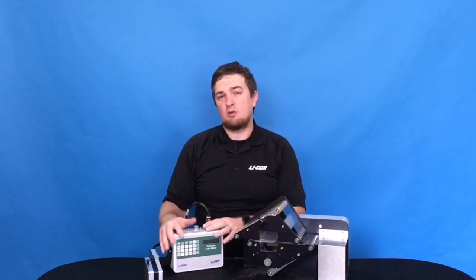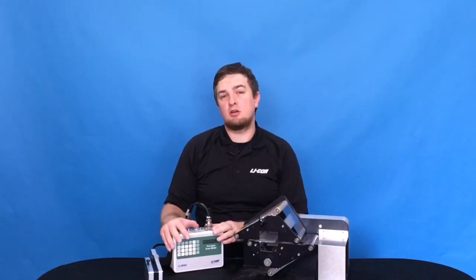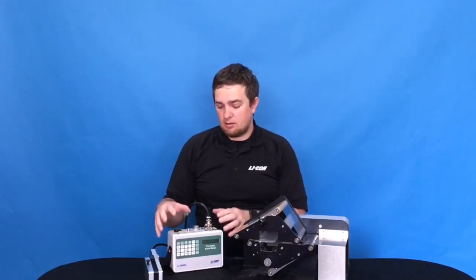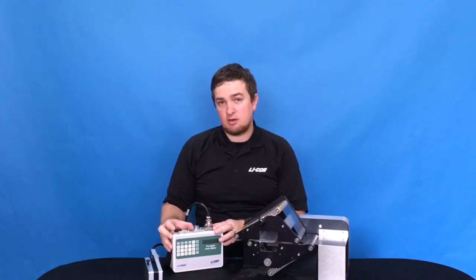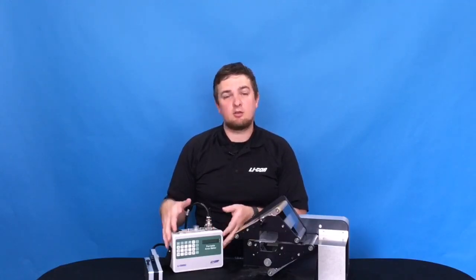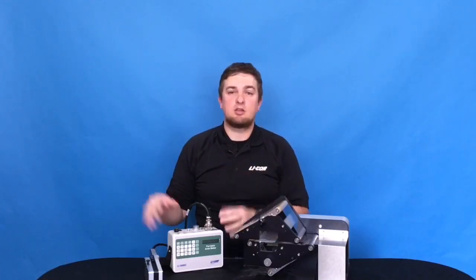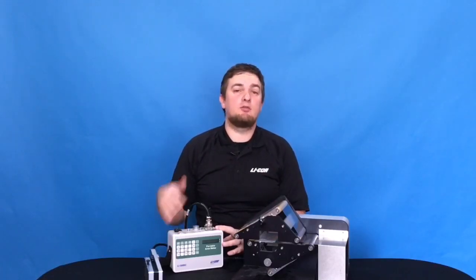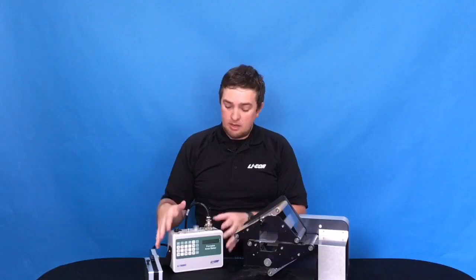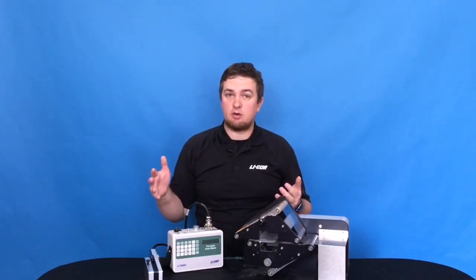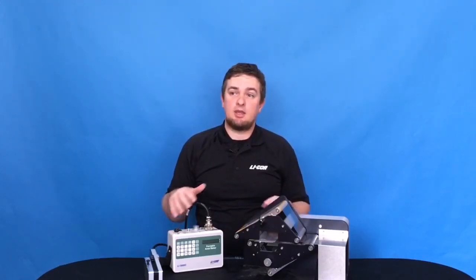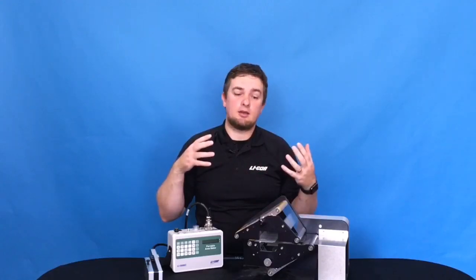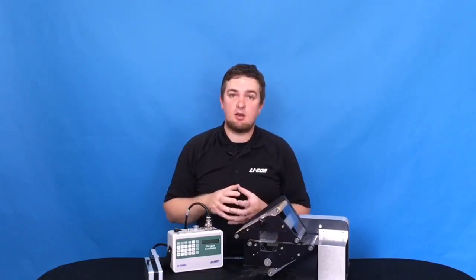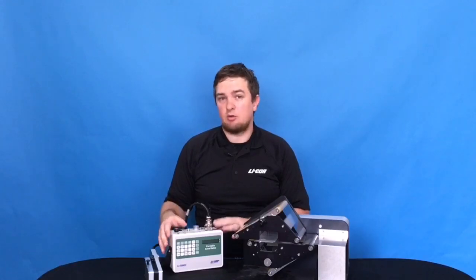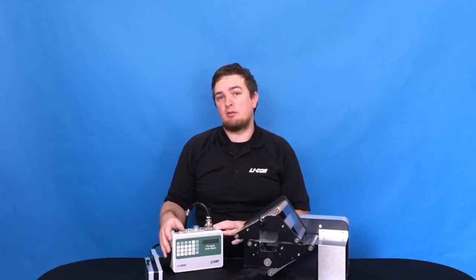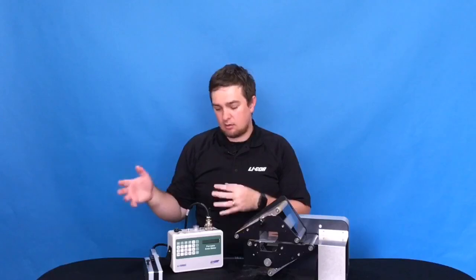I would say the most important thing is to make sure that you charge the batteries frequently. This instrument, the batteries do die if this console is kept in a storage container for a long period of time without frequent charging. So the battery itself runs for about 12 hours when it's fully charged. If you are seeing that your battery is not lasting that long in the field, you may need to replace it. Order a new battery from LI-COR and take the old one out and put the new one in.